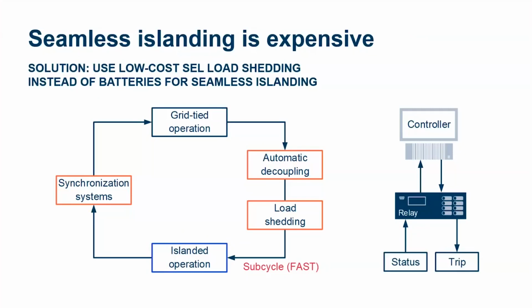Once you're islanded, and by the way, a power system cycle is about 16 milliseconds in North America and 20 milliseconds on the 50 hertz grids of the world. So in less than 16 milliseconds, our relays will have asked either a microgrid controller and/or other relays to please trip load and equalize load to generation. At that point, you survive. That separation and now survival to an island.